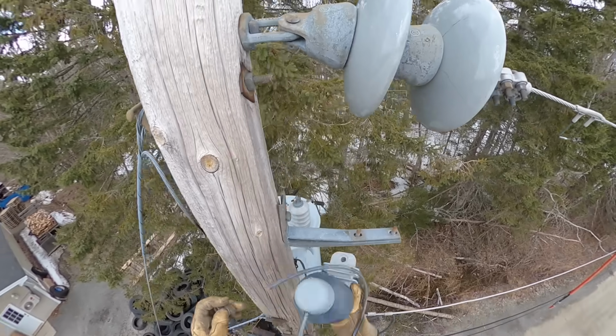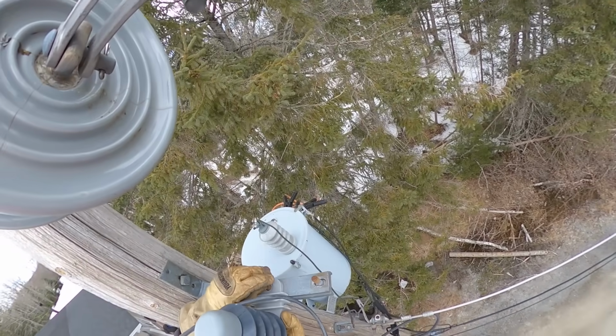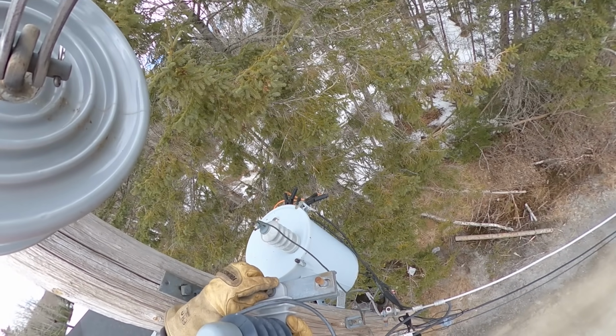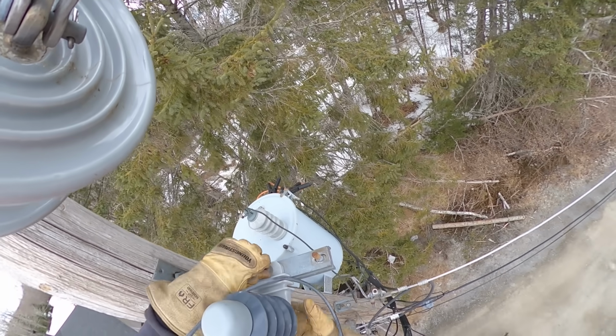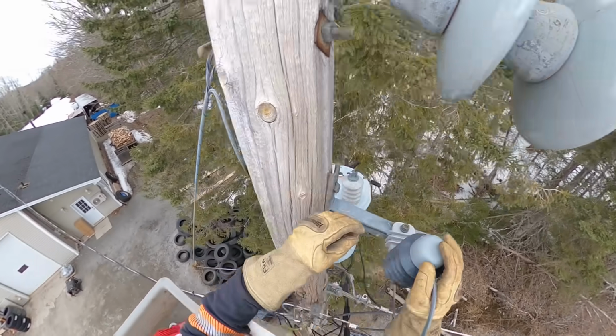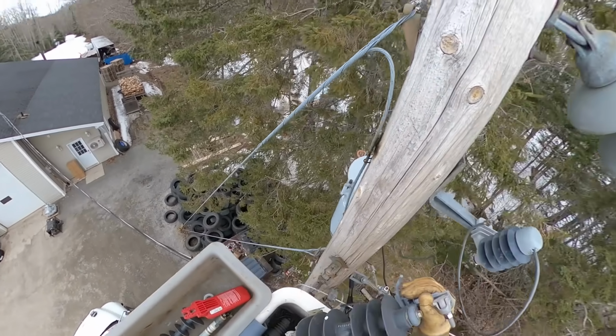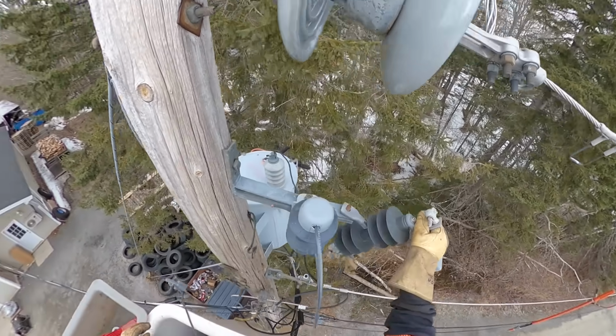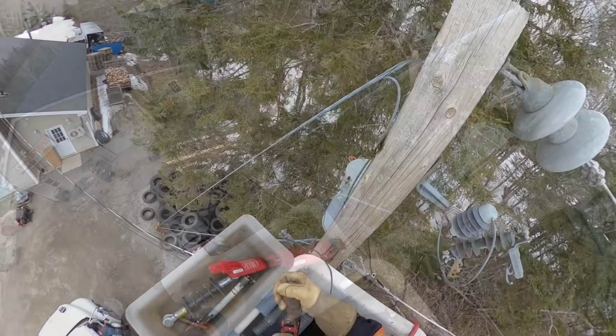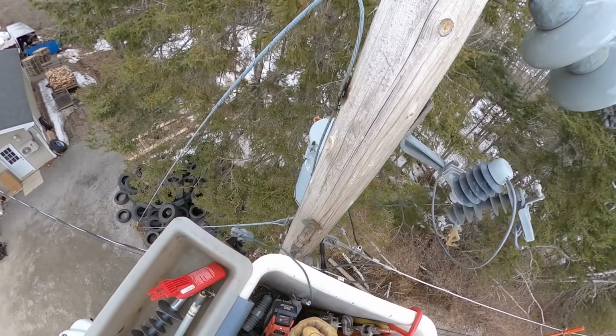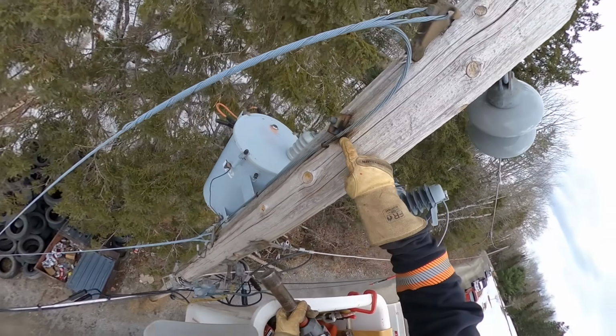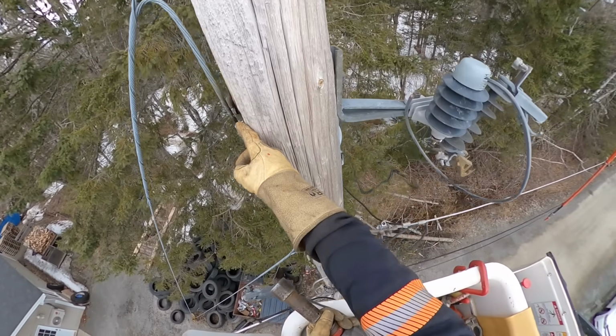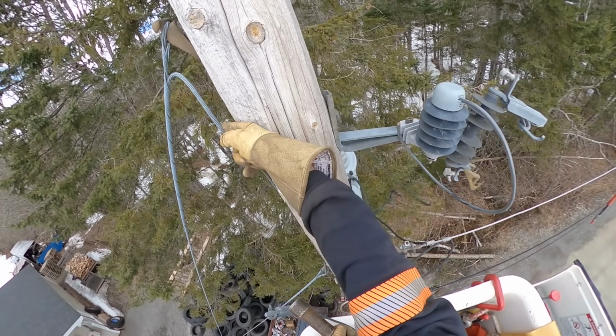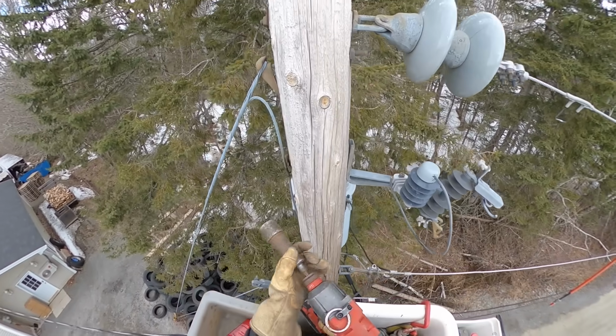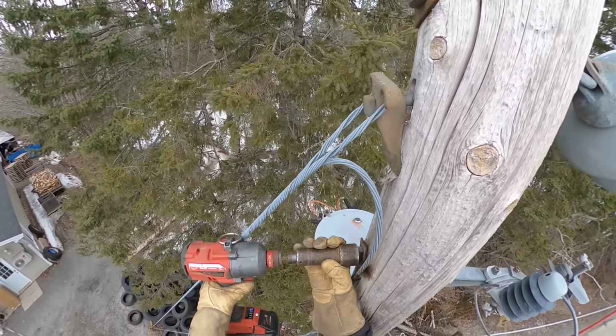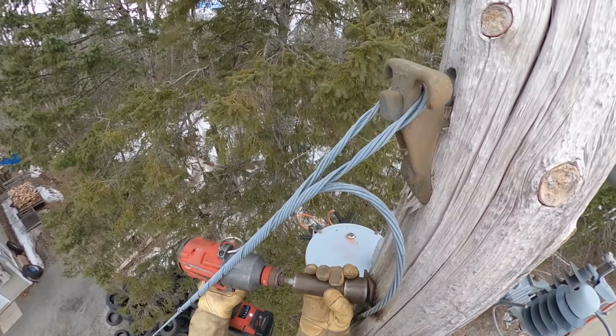So the new lightning arrestor we're putting on, it's a 10 kV arrestor, and it's a new polymer type. The polymer stuff now, it's much more UV resistant than the traditional plastics that were installed on poles 40 years ago. And you can see right there that primary voltage traveled through that bolt towards that guy wire. So we're just going to snug that up. That had nothing to do with the arc.